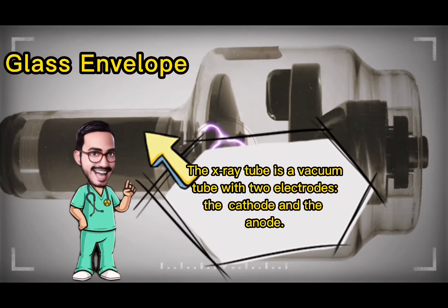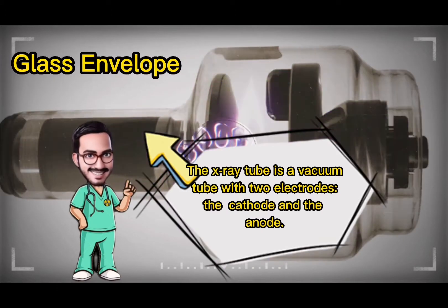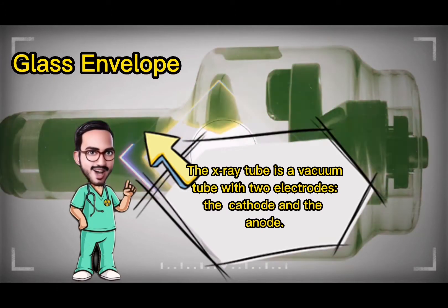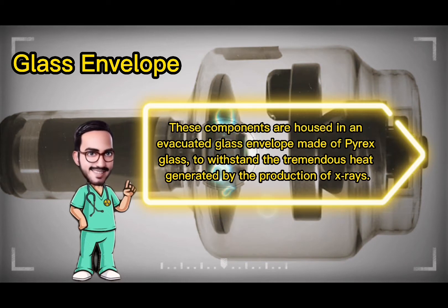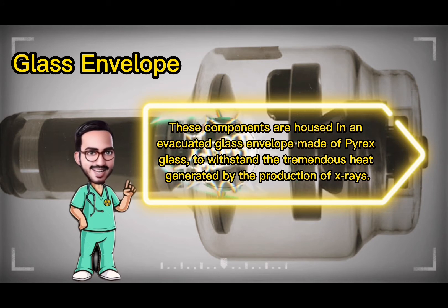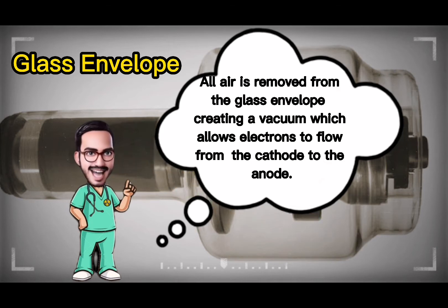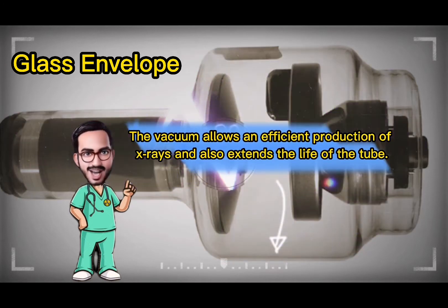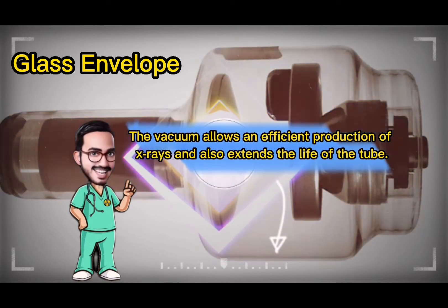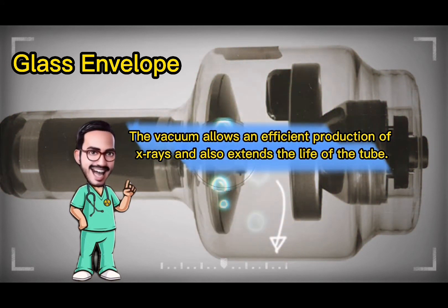The x-ray tube is a vacuum tube with two electrodes, the cathode and the anode. These components are housed in an evacuated glass envelope made of Pyrex glass, to withstand the tremendous heat generated by x-ray production. All air is removed from the glass envelope, creating a vacuum which allows electrons to flow from cathode to anode and enables efficient production of x-rays, also extending the life of the tube.